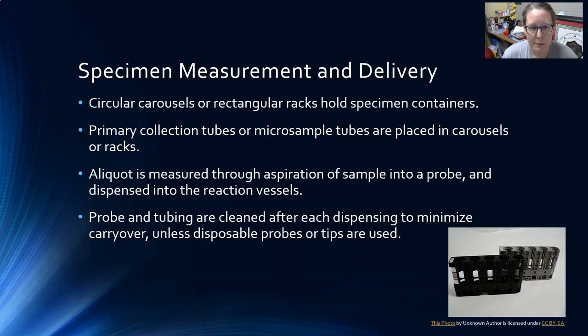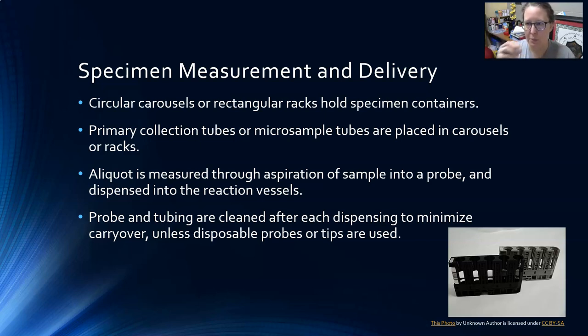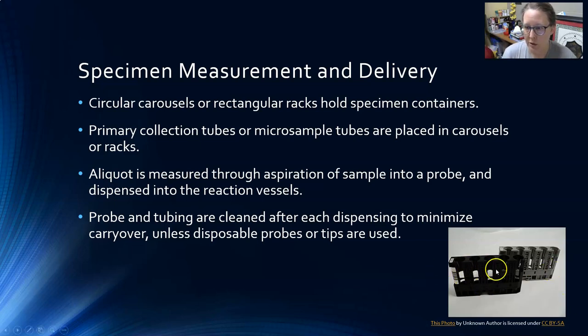Next is specimen measurement and delivery — loading the specimen on the analyzer and then the specimen being sampled and delivered to reaction vessels. Circular carousels or rectangular racks can hold specimen containers, so that could be the primary tubes loaded straight onto the carousels or the racks.